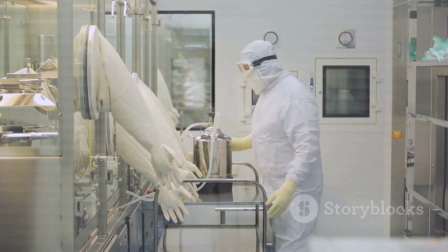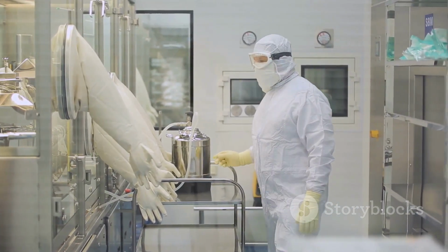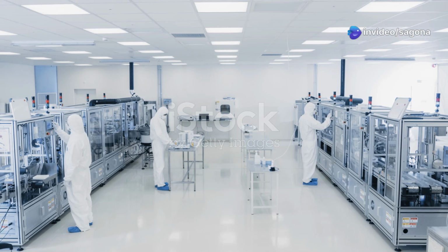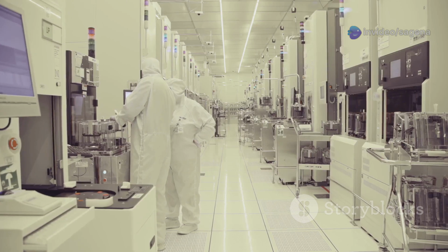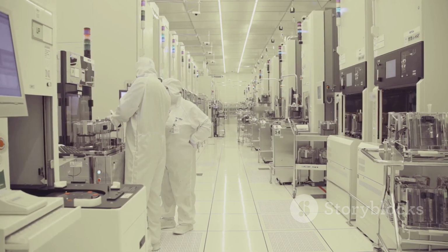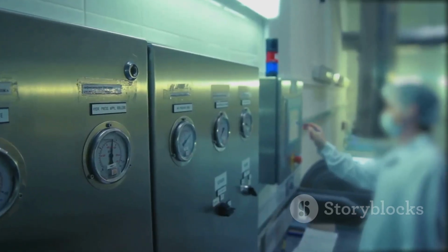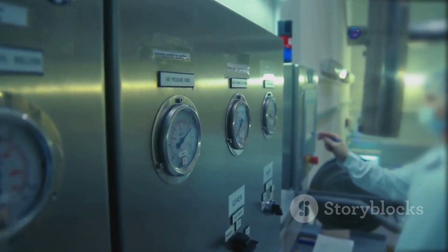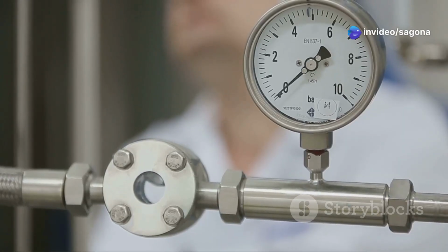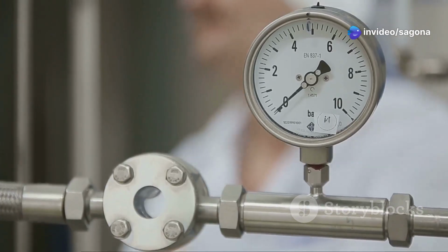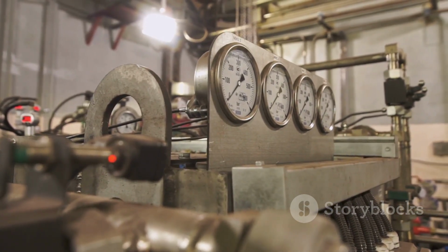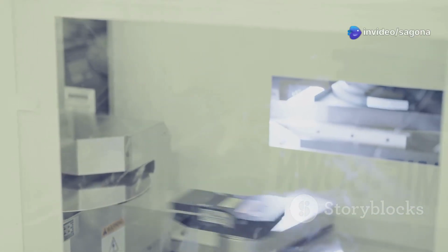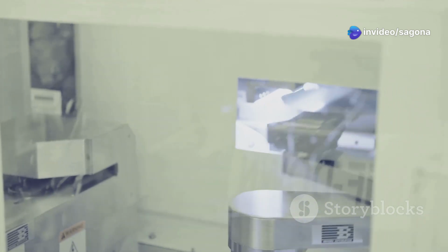In pharmaceutical manufacturing, we have different levels of cleanliness, often called grades. Think of a grade B clean room as being incredibly clean, where sterile products are prepared. Right next to it, you might have a grade C area, which is still very clean, but not quite as pristine. To protect the grade B room, we make sure its air pressure is higher. We typically aim for a pressure difference of about 10 to 15 pascals between these areas. A pascal is a unit of pressure. It's very small, but in this context, it's a big deal. This ensures a constant, gentle flow of air from the cleaner grade B room to the less clean grade C room, forming an invisible shield.